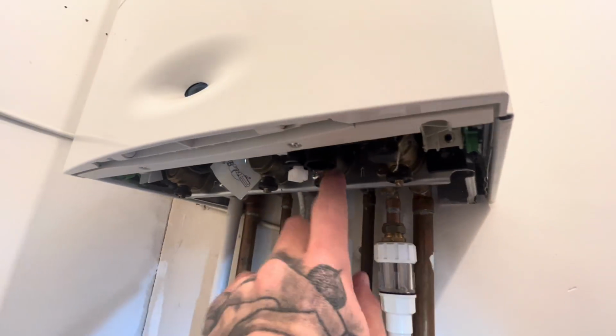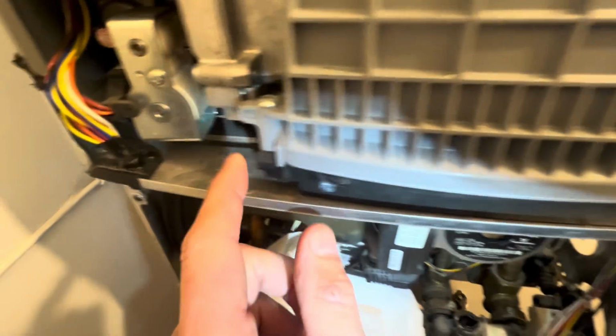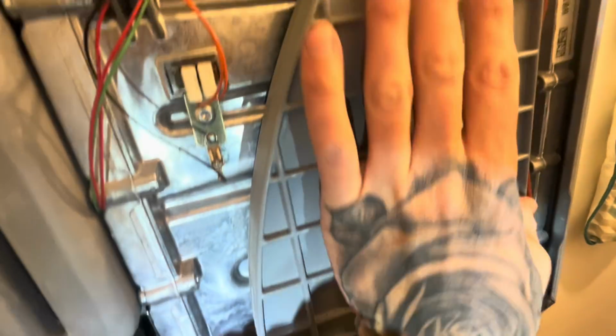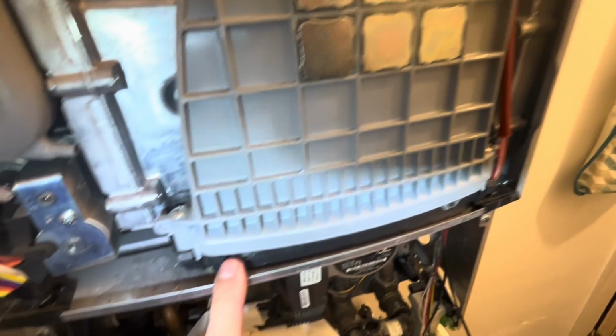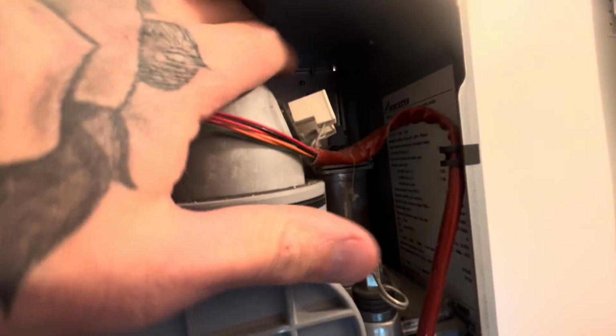The key in might not help things, but I service this I think every single year and I've never pulled it down with the key in, and like I said, that one's broke. So I had an issue with the sump seal, which wasn't really a problem to change. It was just them 2 screws, and that slides up and the turret comes off. We've superseded that now, so that's not really an issue anymore. They had an issue with the auto air vent weeping at the back.